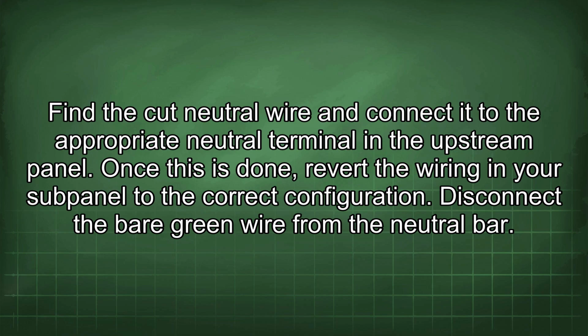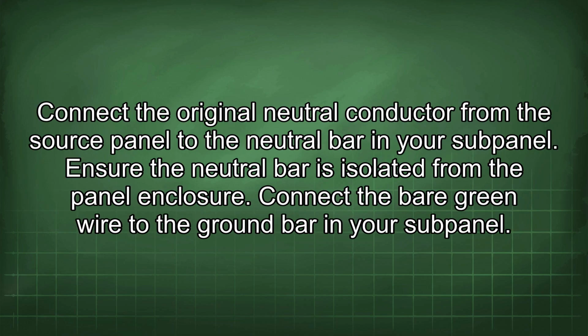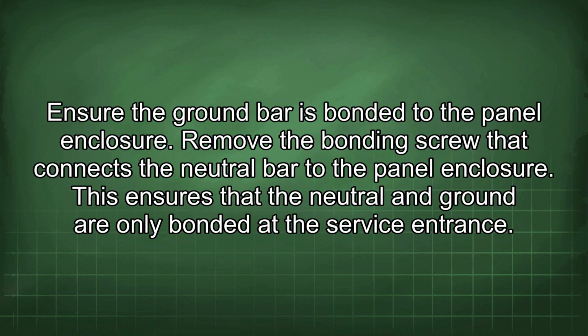Disconnect the bare green wire from the neutral bar. Connect the original neutral conductor from the source panel to the neutral bar in your subpanel. Ensure the neutral bar is isolated from the panel enclosure. Connect the bare green wire to the ground bar in your subpanel. Ensure the ground bar is bonded to the panel enclosure.